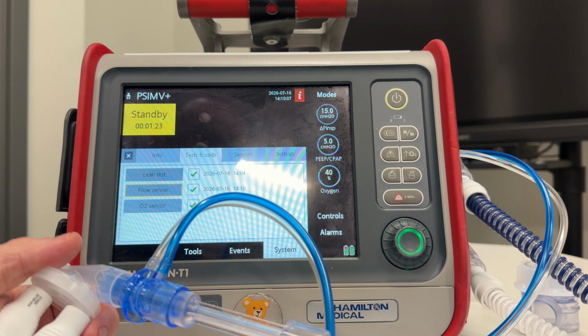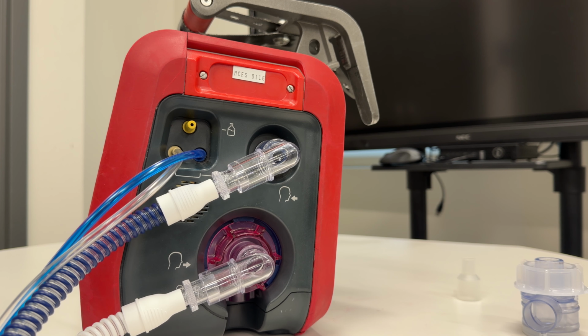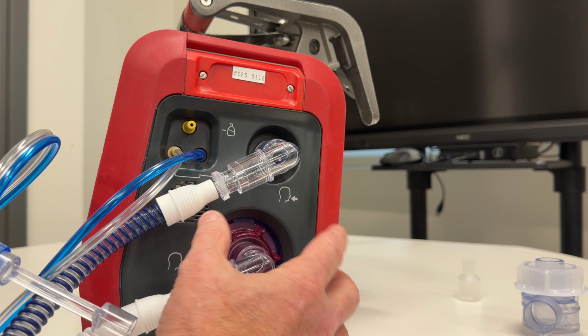They're pretty simple. As long as you follow the directions, they are going to pass unless there's something wrong. Every once in a while, if you do get a failure, I've seen this a few times, and you've done everything right, if you reach inside of this housing here, sometimes you run your finger around, I've found a crack in that blue housing. And if it's loose or it wiggles at all, there's a problem with it. Somebody's dropped the ventilator or something has happened to it, and that is out of service at that point. You need to swap it out. But that is after multiple failures. Make sure you check that, just kind of feel and make sure it's not loose.